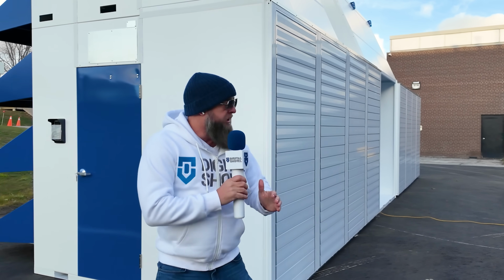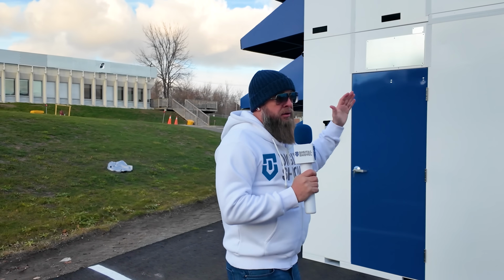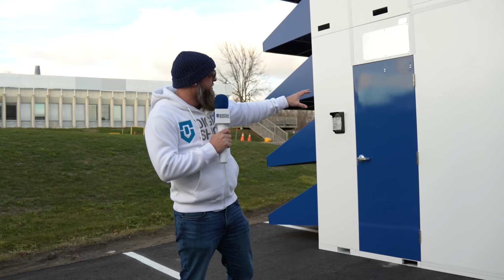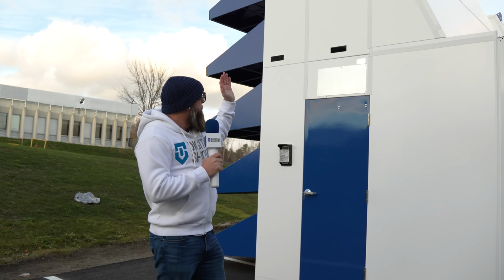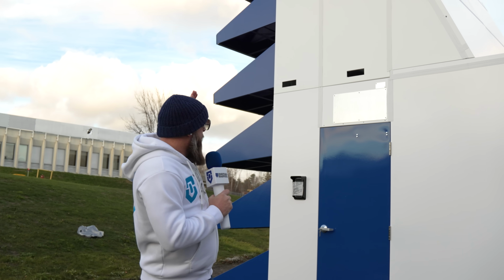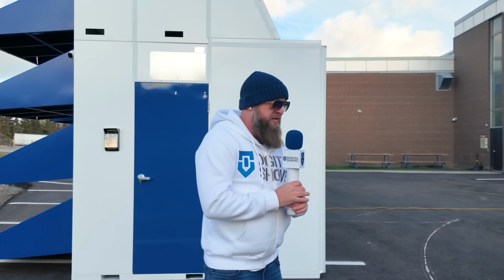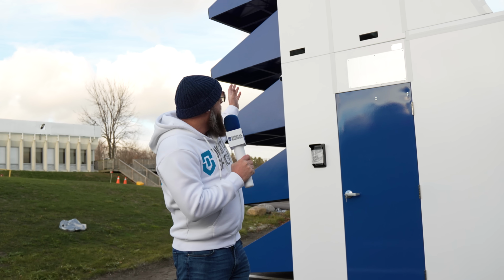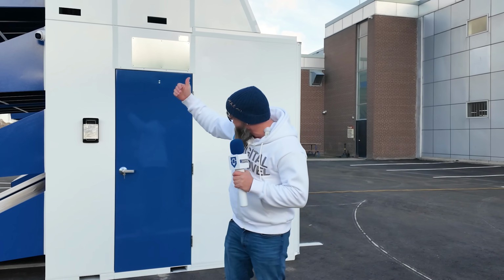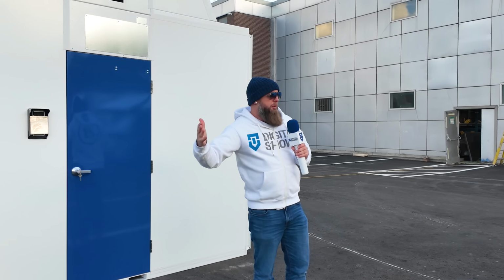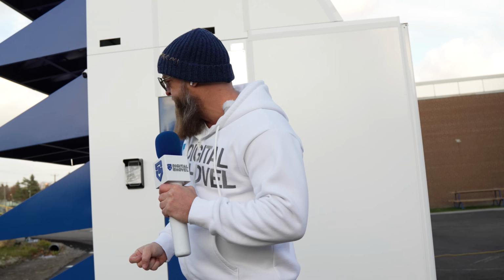Up top, you've got a second level here. I'll show you from inside, but that second level is just for additional air intake. There are only miners here on the lower level of the pod. The upper level of the pod has 3 additional air intakes, which would have 24 by 24 by 4-inch deep pleated filters, 18 per pod, so you've got 36 total top and bottom, bringing all of that air down and through and into your miners, reducing the amount of air restriction that would normally be caused by if you just had one wall of filters sitting here. We have, on a single level, 60% more surface area of filter intake, and when we do double, we're increasing that by another 100% on top of that.